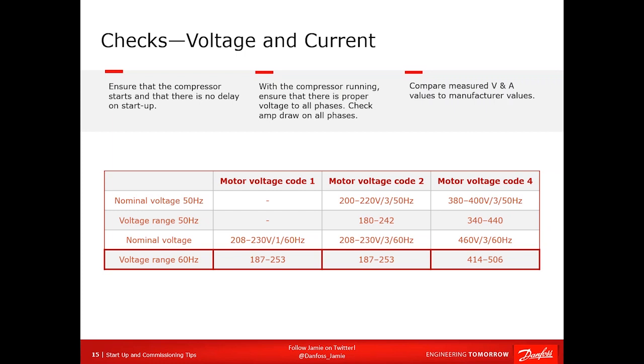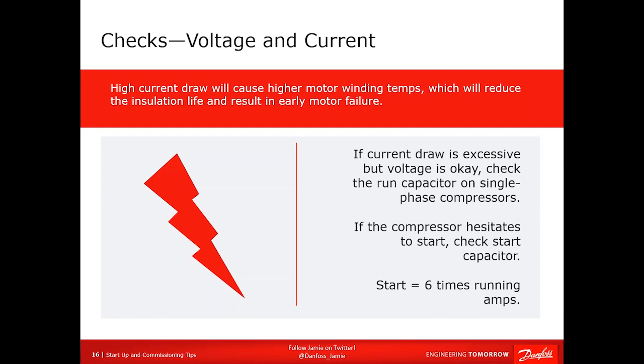Insulation life is directly related to temperature, and temperature is directly related to current. And as your voltage goes down, or stranger still, goes above a certain value, your current goes up. So the compressor is going to operate hotter at higher current, lower voltages than it will at correct voltage. If you get one of those strange situations where your voltage is okay, but your current is high, and you've checked the operating conditions, the pressure and temperature of the evaporator and condenser, you've referred to the application manual, and something is just not jiving, but your voltage is fine. There's a couple of things. One, check the run capacitor if there is one, okay?